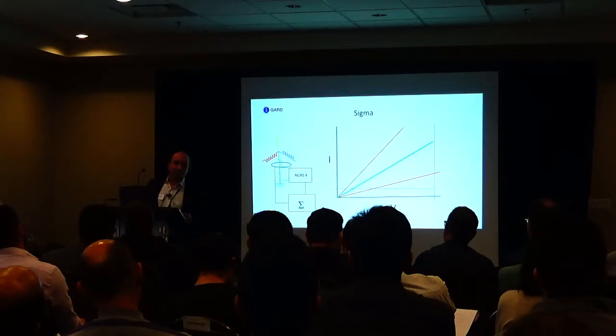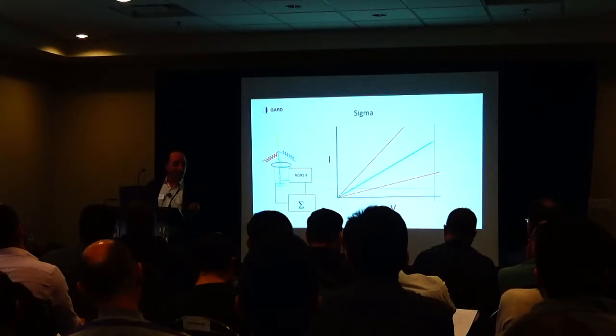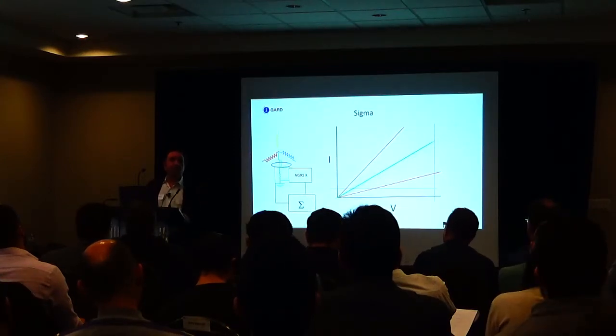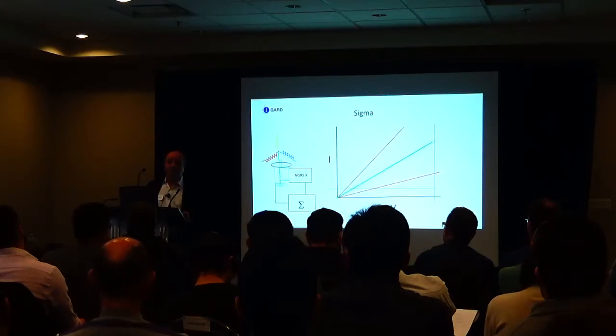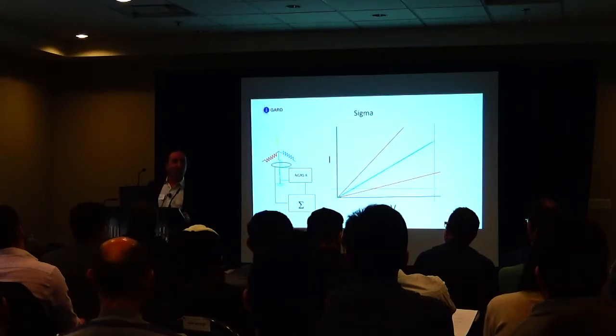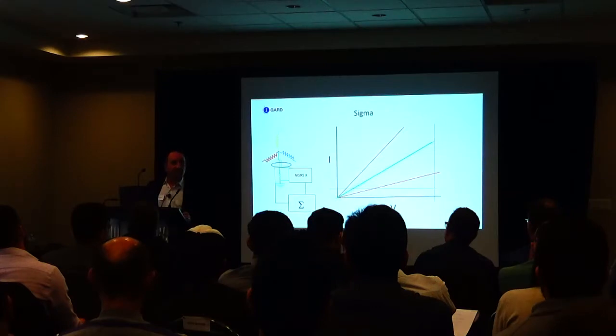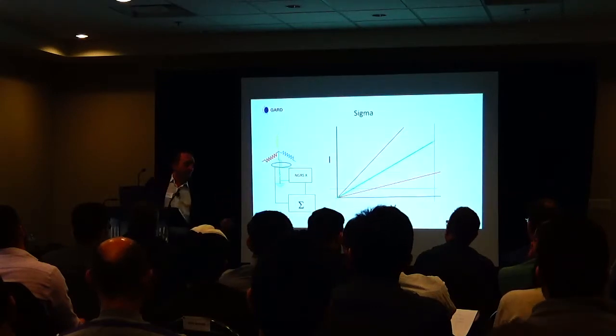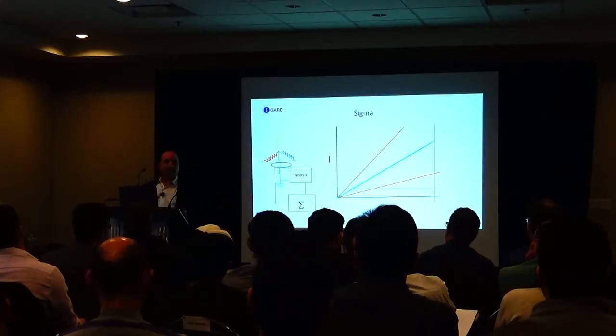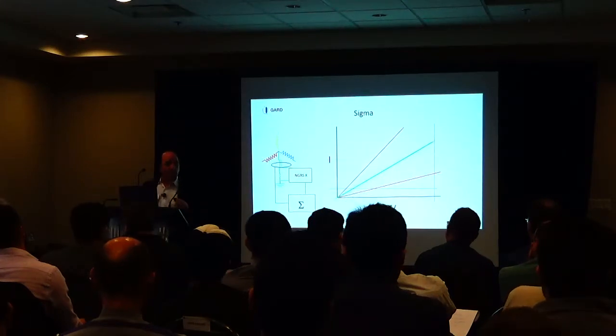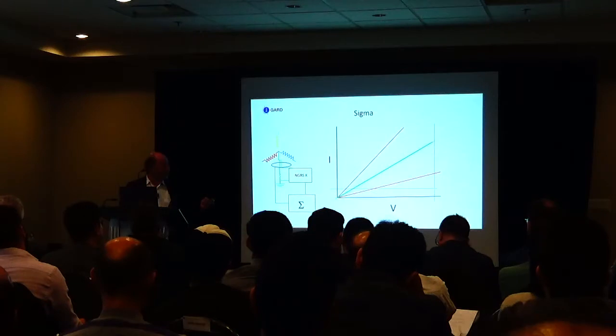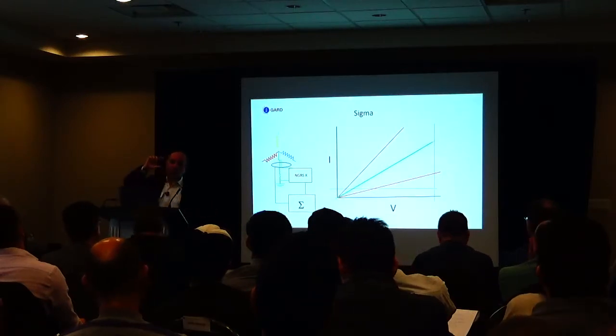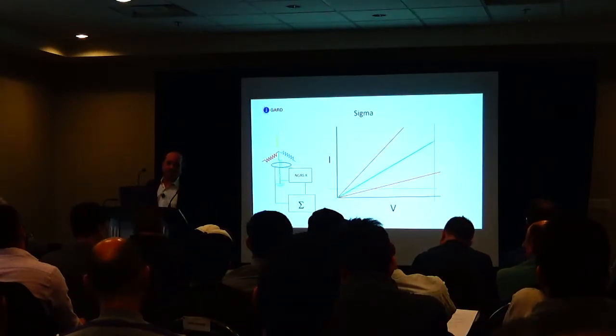If we don't have that capability, say for example, in the mining industry, we have to do this even when the voltage is off. We have to monitor the integrity of the resistor when the voltage is de-energized. We do that through injection, and we can actually tell if the resistor is open or short-circuited, even with YY connected PTs, and soon, even if there's a transformer coupled to a resistor on it.